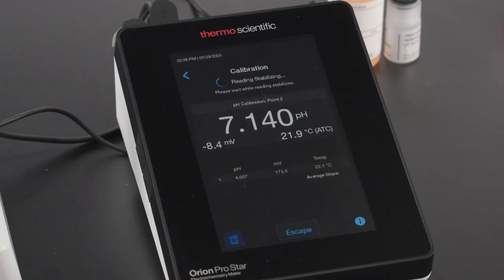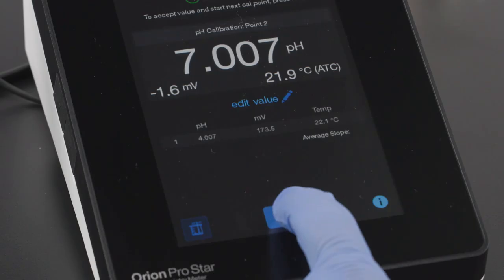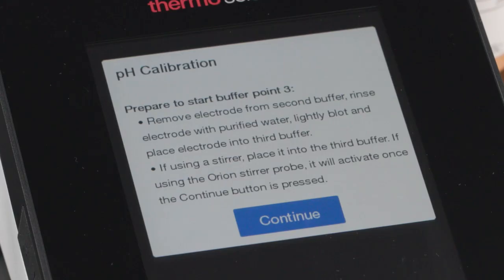It's best to calibrate at 2 or more pH values to determine calibration slopes, which tell us about the validity of our calibration. The reading has stabilized and the meter has locked on the correct pH value for the pH 7 buffer at the measured temperature. Tap Next to accept the second calibration point and prepare for the third calibration point at pH 10.